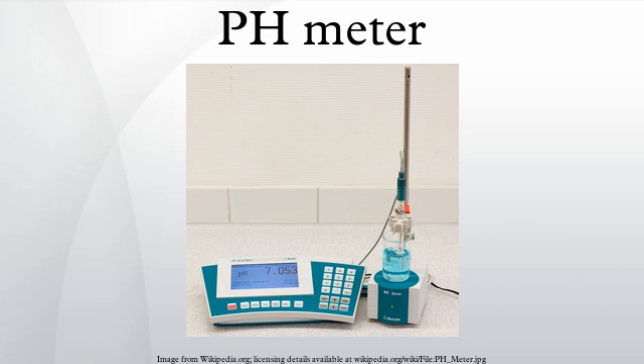Cleaning and troubleshooting of the glass probes. Occasionally, the probe may be cleaned using pH electrode cleaning solution. Generally a 0.1 M solution of hydrochloric acid is used, having a pH of 1. Alternatively a dilute solution of ammonium fluoride can be used. To avoid unexpected problems, the best practice is however to always refer to the electrode manufacturer recommendations or to a classical textbook of analytical chemistry.